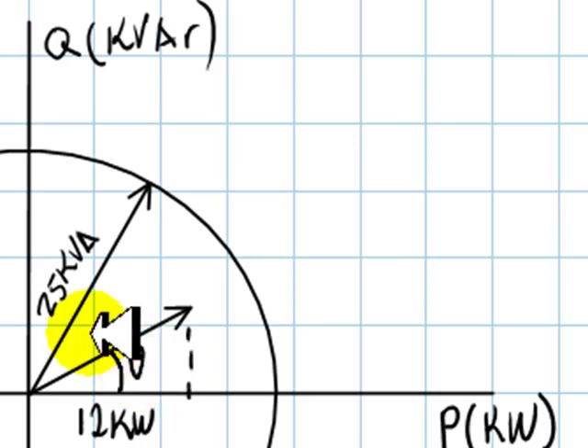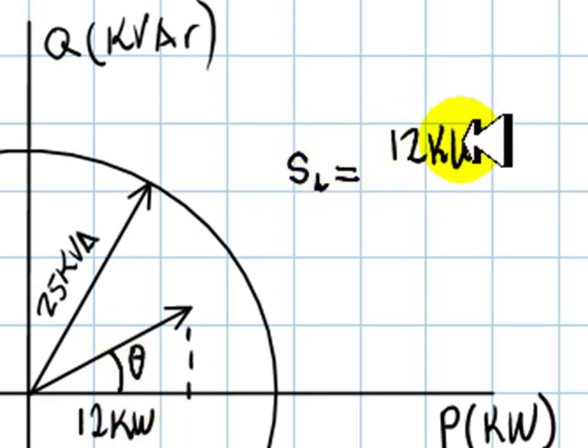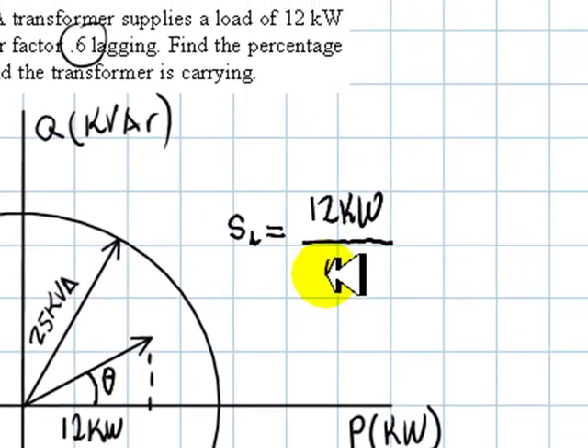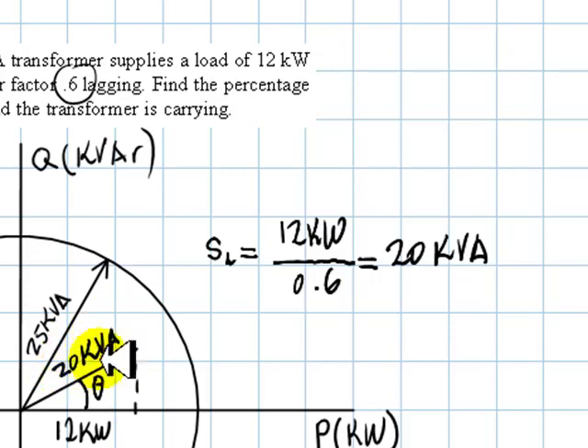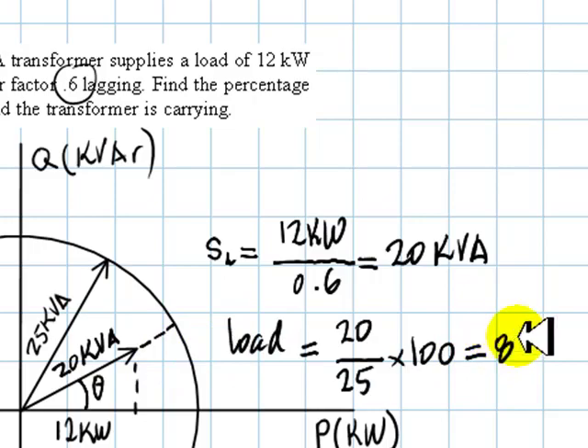The apparent power of the load is 12 kW divided by the cosine of the angle, 0.6. That is 20 kVA. So that load is a load of 20 kVA, which is clearly not up to the full capacity of the transformer. It's not up to 25 kVA. The transformer is loaded only up to 80% of its capabilities.